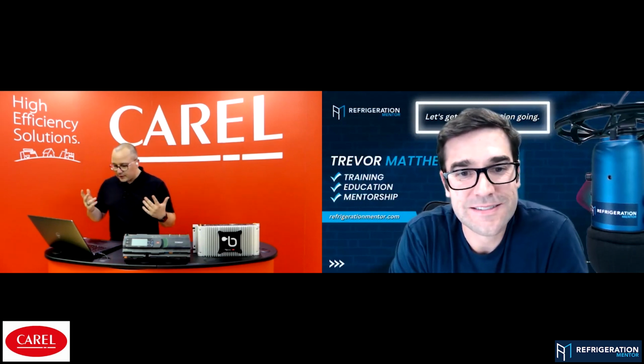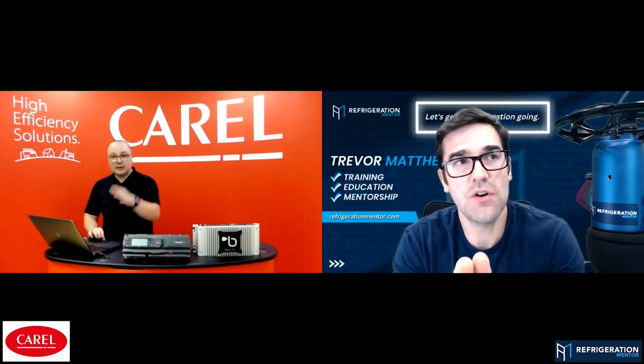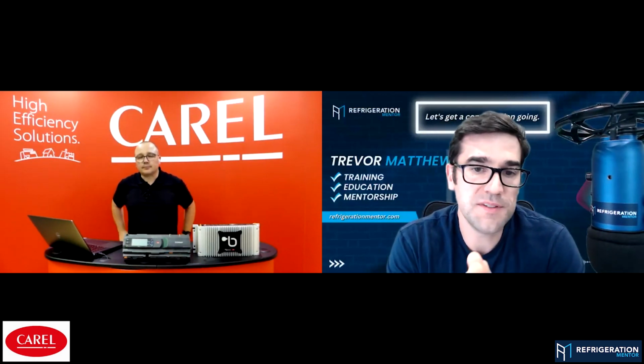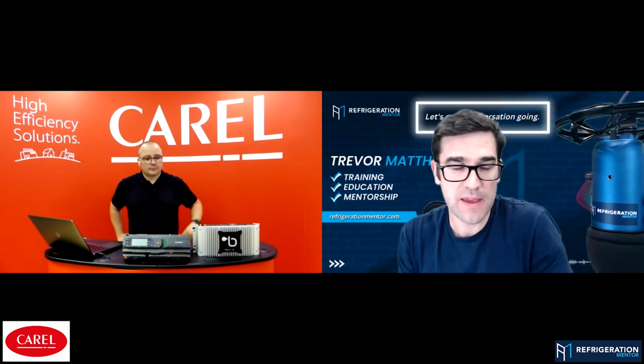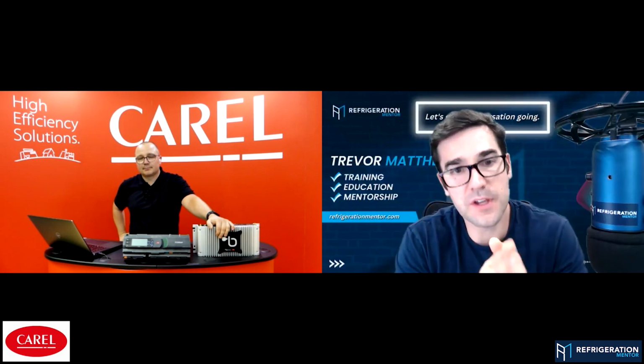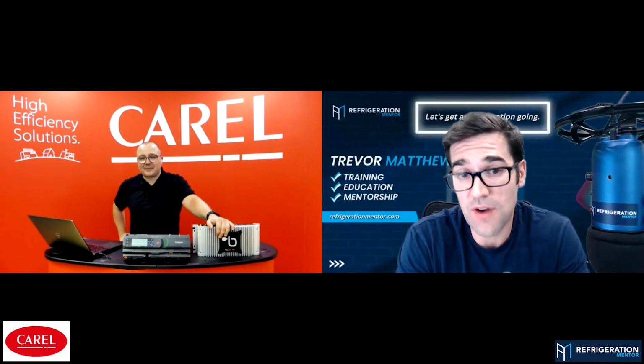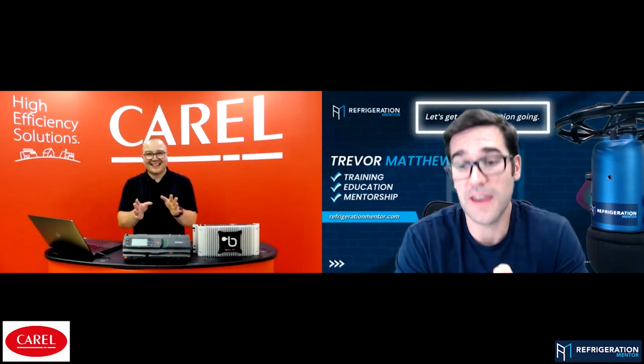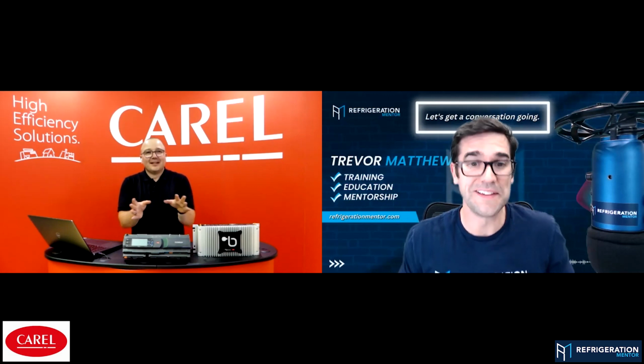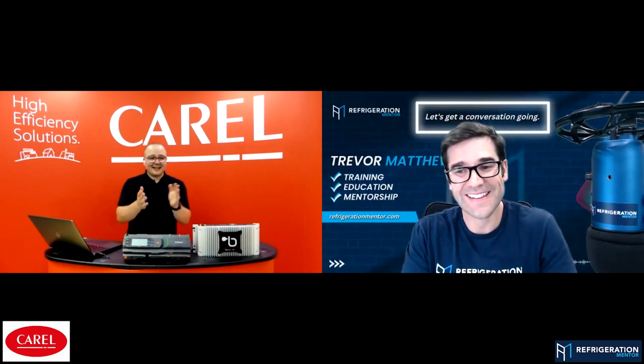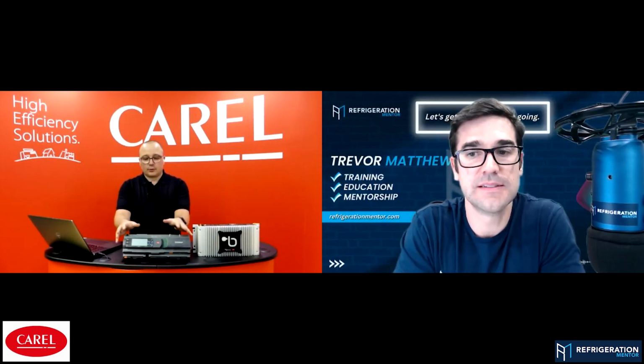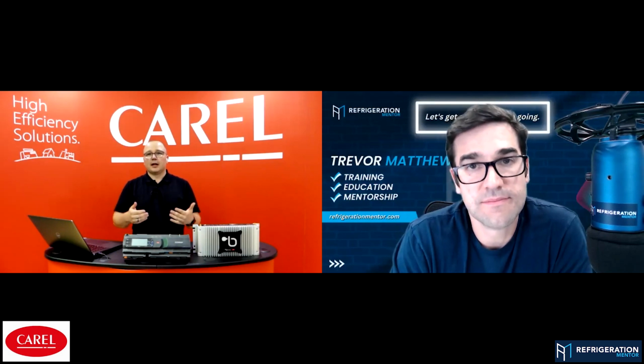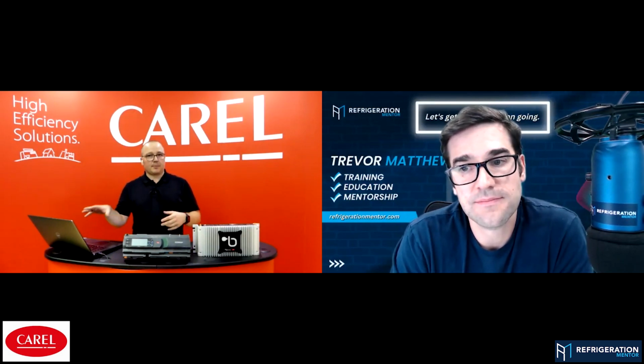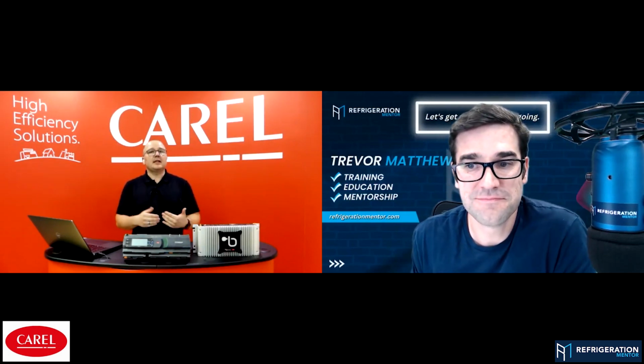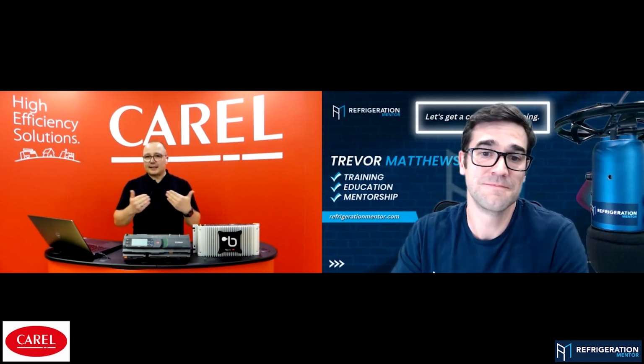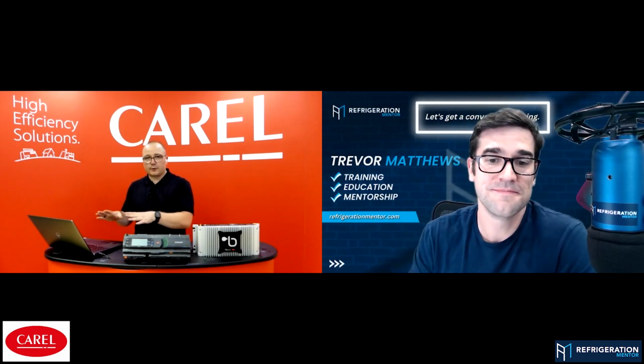Yeah, let's start with a short look into the problem. Let me ask you a question first, though. If a contractor or manufacturer builds a piece of equipment and doesn't have the monitoring system, can you go into the controller and still get some information and graphs? Yeah, it depends. Okay. And every time the big answer to all questions are, it depends. That's refrigeration for you. Exactly. You have many possibilities to go directly into this controller and find information and to read some log graphs out of it. If you have your laptop and you connect it to the controller, you can see some live data and even some stored data, depending exactly on the system, how it's set up, and what software you are using.